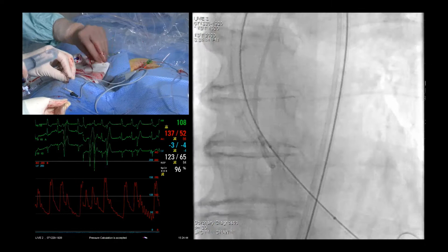So I understand you intend... Do you intend to pace only during the valvuloplasty or also during the valve implantation? Only during the valvuloplasty. And of course, if pacing on the guide wire should work, you need to have some isolation on the guide wire. So if, let's say, the patient develops third-degree AV block, you cannot remove the system. You need to put an RV pace lead in before you take it out, because if there's nothing on the guide wire, you can't really pace.